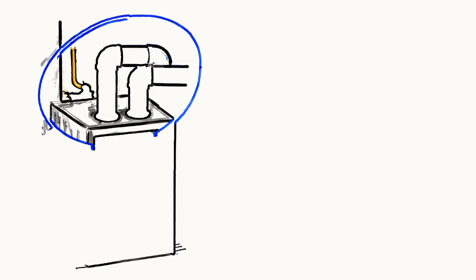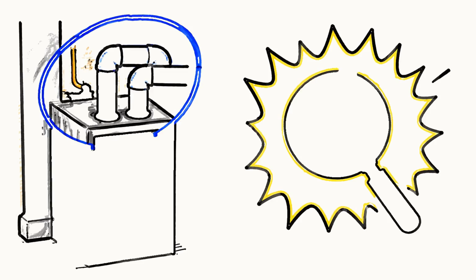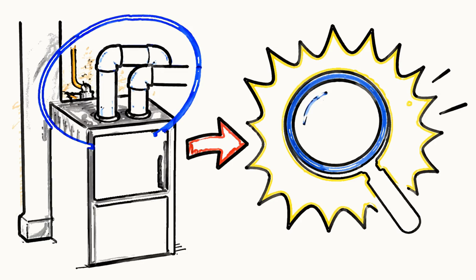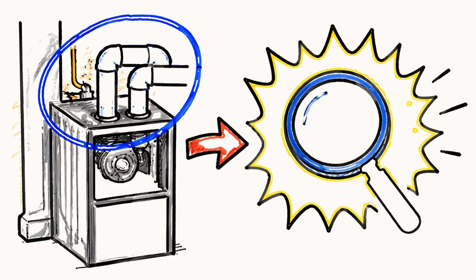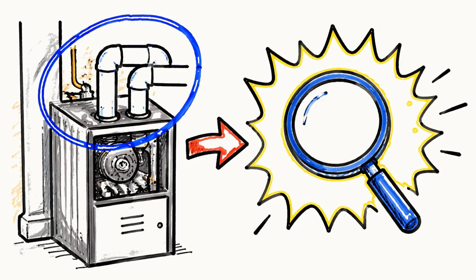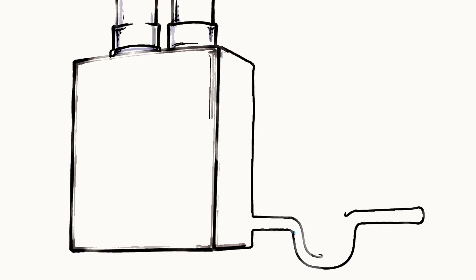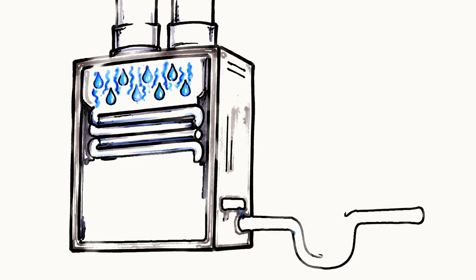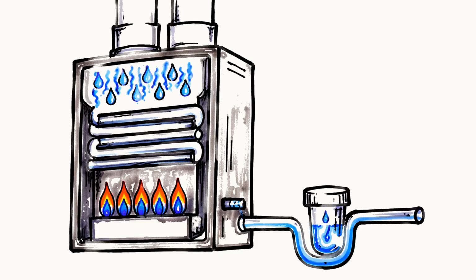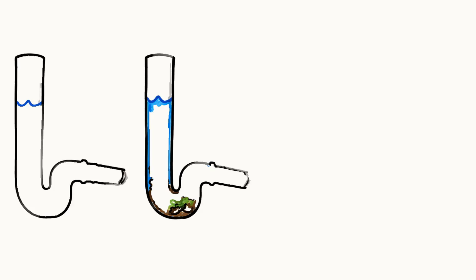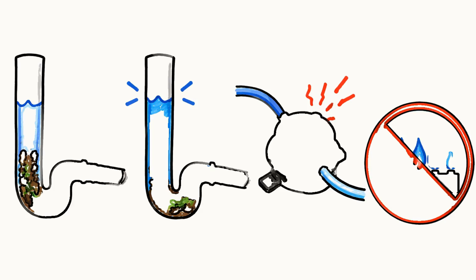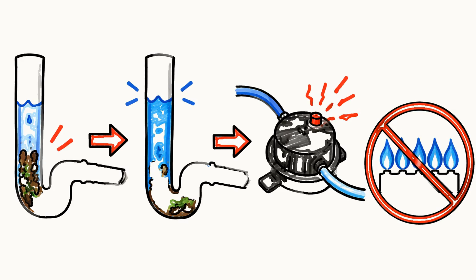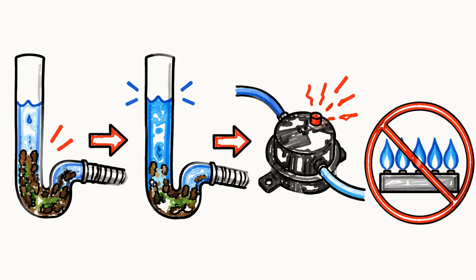If your furnace is a newer high-efficiency model, the kind with white plastic exhaust pipes instead of metal, there is one more common cold air cause worth checking. These units create water when they burn fuel, and that water drains out through a small tube and trap. If that drain clogs with gunk, the water backs up and trips a safety part called the pressure switch, and the furnace simply refuses to light.